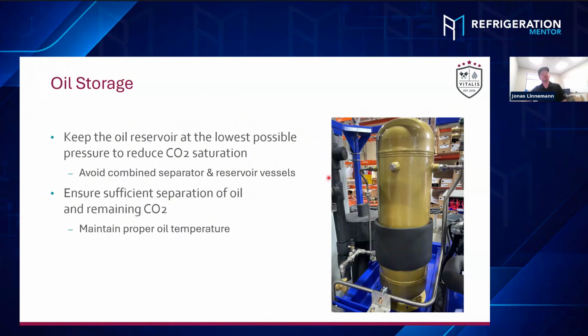So I see you got insulation on there. Is there like a heater element in that one? Exactly. So that's another thing. By lowering the pressure, you can reduce the CO2 saturation, but also by keeping it warm, because the warmer you keep the oil, the more CO2 can basically gas out of the oil.